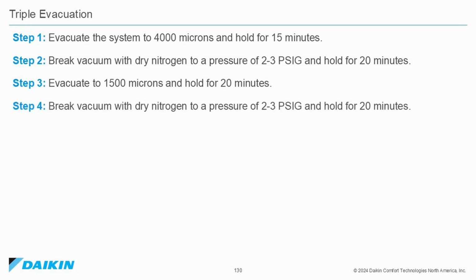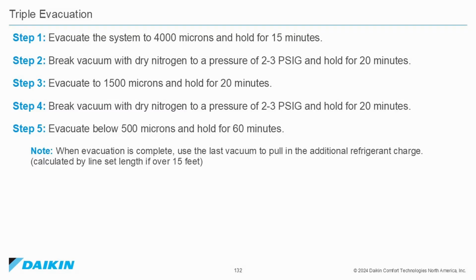Step 4. Break that vacuum with dry nitrogen to a pressure of 2 to 3 psi and hold for 20 minutes. Step 5. The final evacuation should be below 500 microns and hold for 60 minutes. When the evacuation is complete, use the last vacuum to pull the additional refrigerant charge into the system, calculated by line set length if it's over 15 feet. The triple evacuation is the only way to ensure a clean, dry, and sealed line set.